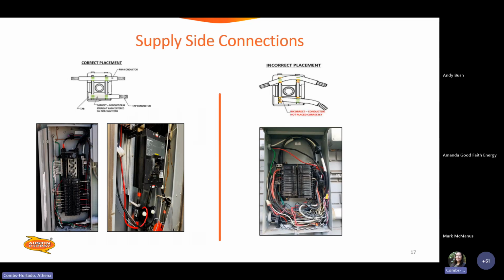All right. Okay. So supply side connectors. So we've got correct placement and incorrect placement. For correct placement, the conductor needs to be straight and centered. Piercing taps need to be installed on a straight run of service conductor. Do not install them where there is a bend in the wire or where there isn't room in the panel. A good rule of thumb is that if you have to apply pressure to reinstall the dead front on the panel, then there is not sufficient room in the panel. And as always, just follow the manufacturer's instructions.